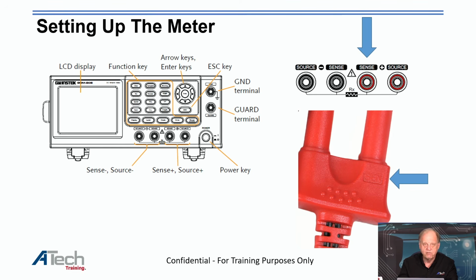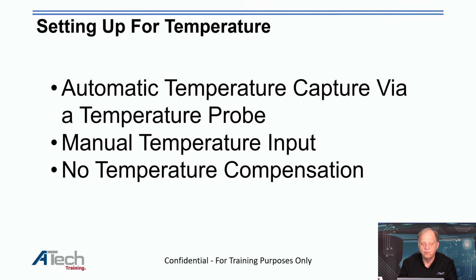Now, if I go to my next screen up here, we have automatic temperature, via a temperature probe. In other words, if you have an automatic temperature probe, it's automatically going to read the ambient air around this tool. That's fine. That works really good. If you don't have that probe, the next thing you're going to have to do is manually input the temperature of the ambient air where you're at, or the room temperature if you're doing your testing, which works out as well as you can. Some of the meters will not have a temperature compensation for it. You cannot put it in there, so you're at a loss of compensating for the temperature. There's one other factor you can do on some tools. They have a conversion factor.